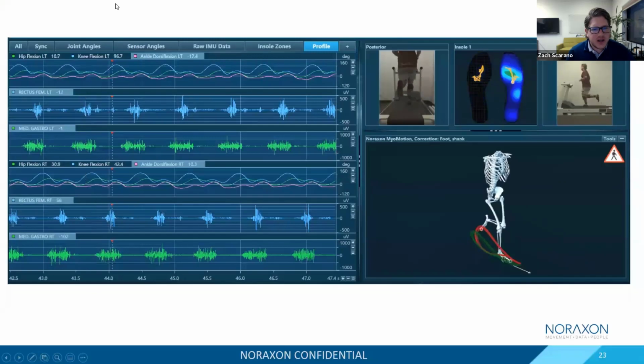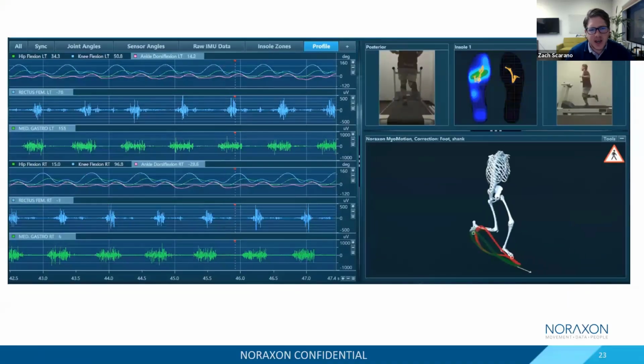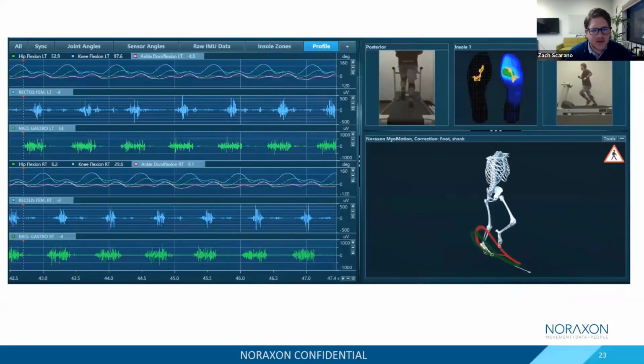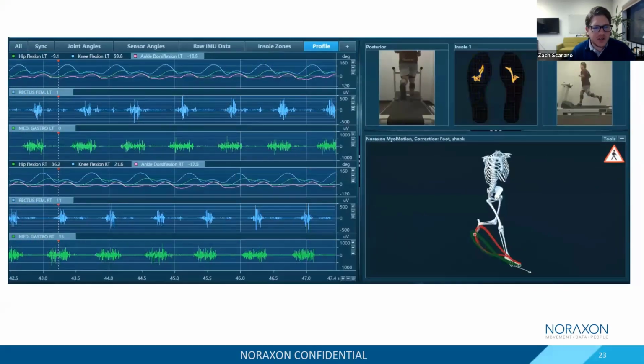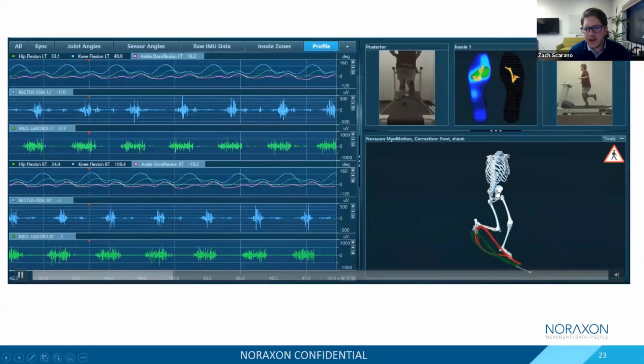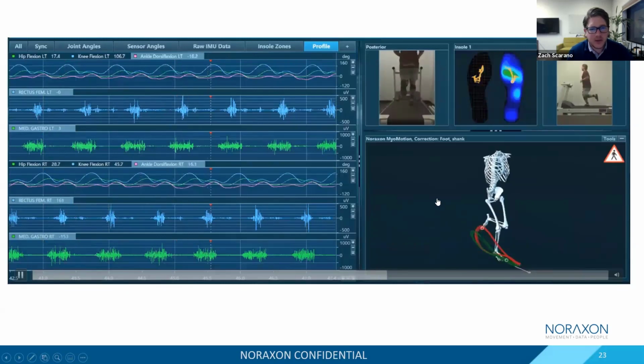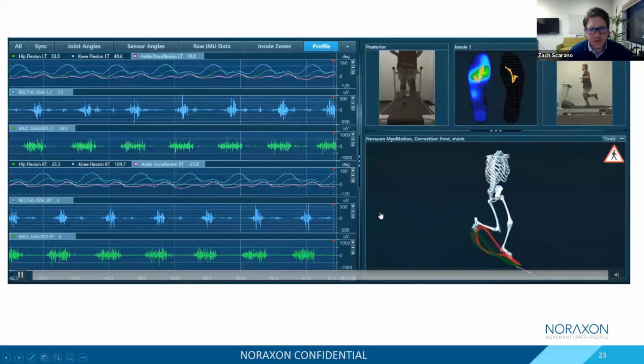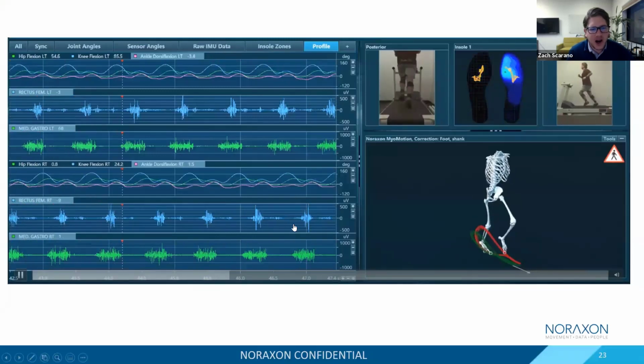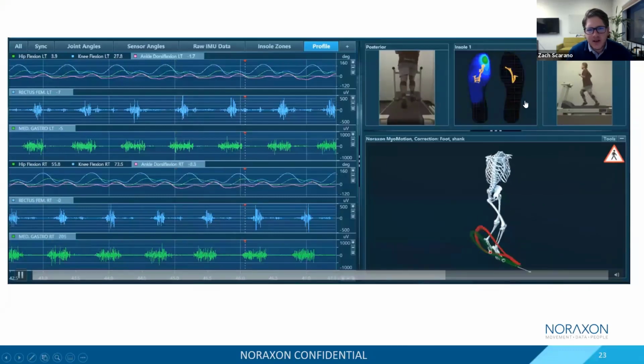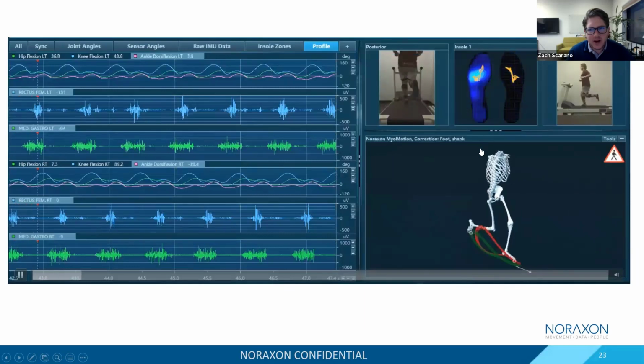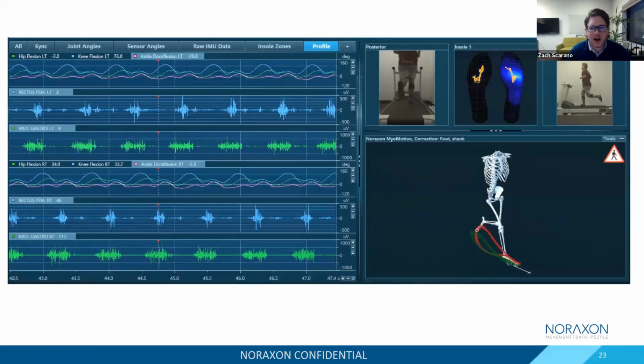And then finally, I just want to show a setup that is that multi-device setup. So again, being able to utilize the advantage of that universal connectivity and have a system that has motion, EMG, pressure distribution, all operating off of one receiver. And so in this case, this would be a great package, for instance, to be able to utilize for running or gait analysis, where we've got the lower body and the trunk for the motion capture. So we can look at the kinematics during those movements. We've got 4 channels of EMG to look at the muscle firing patterns as it relates to those movements. And then we have the Ultium insoles implemented as well to look at that pressure distribution, look at the contact patterns when somebody is walking or running.